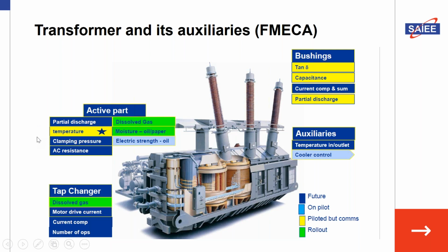On the tap changer, for instance, we do similar checks on the gas, but we could also be monitoring the motor drive current to see how much work it's doing as it powers itself to tap at different settings, and so on. For other auxiliaries like fans, we can look at cooling controls and so on.